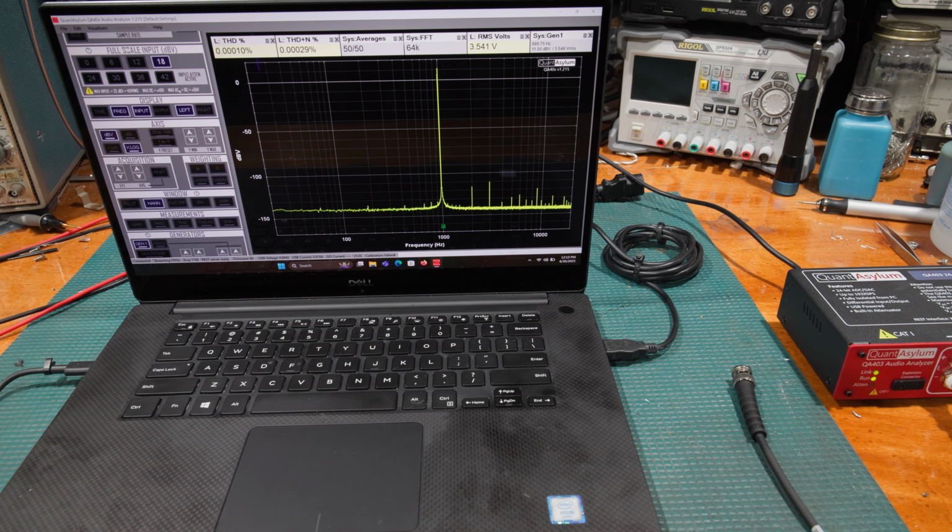Today on the bench we have a discussion about oscillators, distortion, and noise parameters. This is growing out of a conversation that I was having with a viewer of the channel. We were comparing a few things on the 8904A. Really, we were talking about whether the shield behind the LCD display mattered in terms of stability and performance. Short answer is I measure some slight differences between the two, with and without the shield.